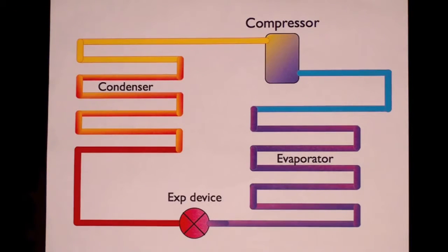The top part of the condenser takes that high superheat off and drops its temperature. When it reaches past the first couple of runs in the condenser, it begins condensing. Now at that point, of course, it doesn't change its temperature. The temperature stays the same, but the refrigerant is turning from a gas into a liquid, all down through this thing. So it's releasing latent heat. When it gets to the bottom of the condenser, the bottom pass or two, it's all liquid.